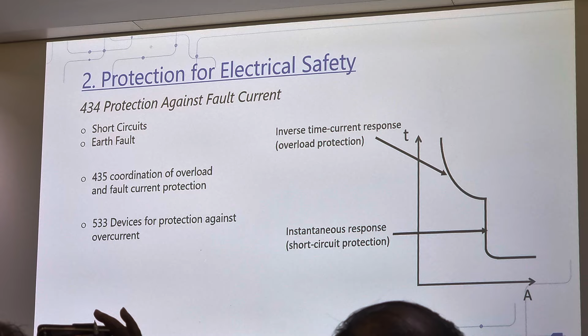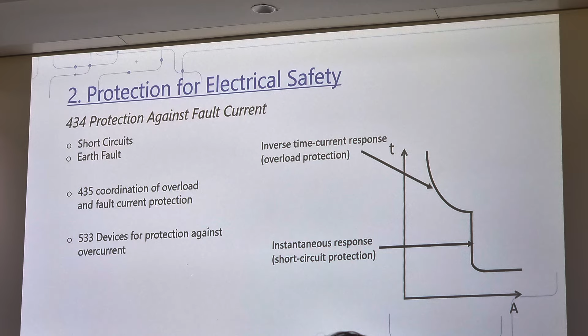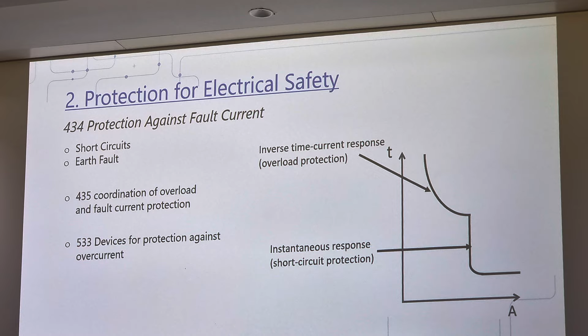So this again is a very typical characteristic of a protective device. This is a circuit breaker. Of course, we still use fuses. We can have different characteristics. MCBs generally have this thermomagnetic characteristic. Thermal means there's the overload reaction. Magnetic means there's a fault current. We want to clear the fault as quickly as possible. So with this thermomagnetic characteristic.